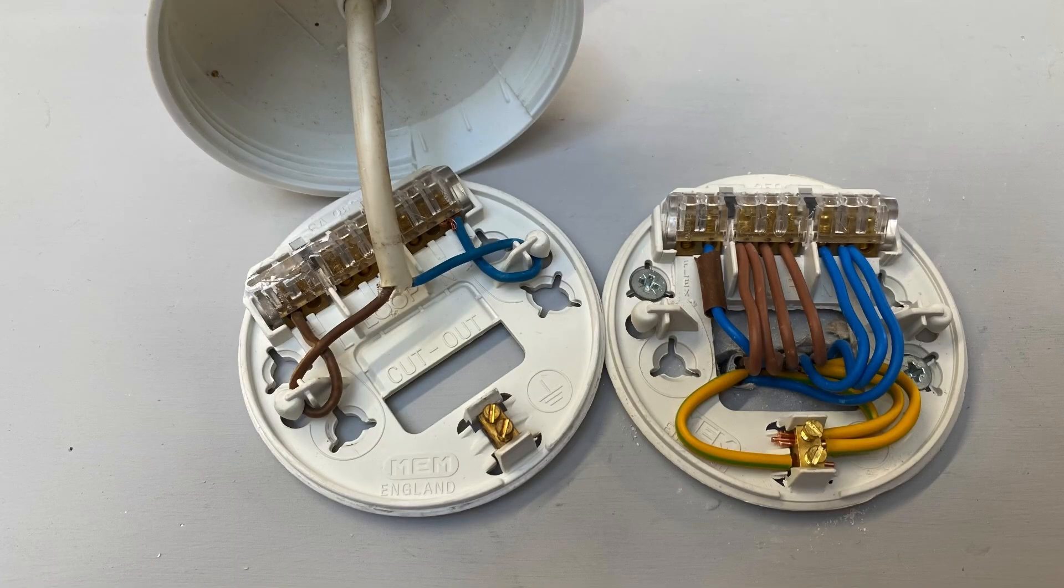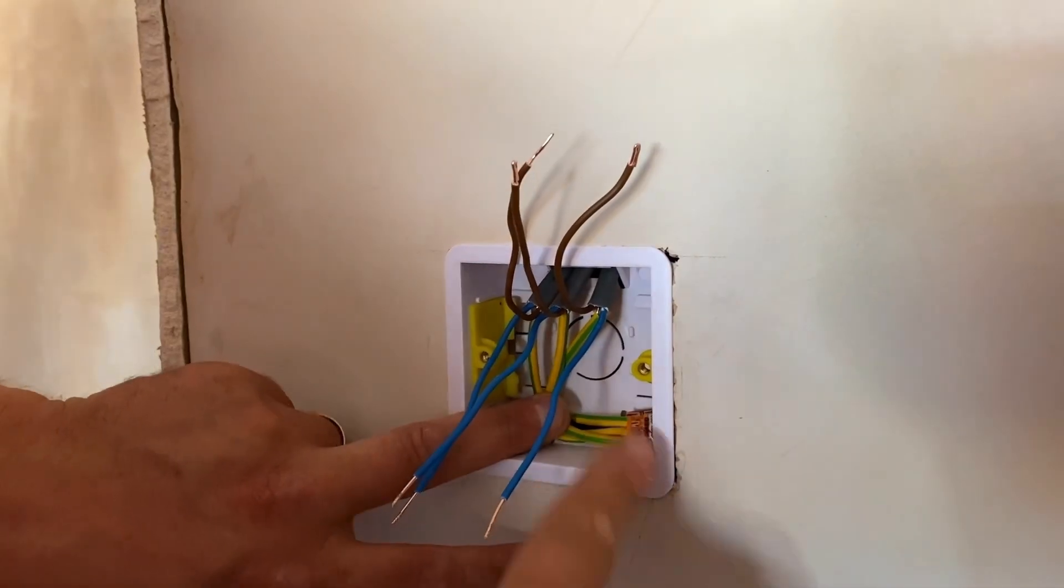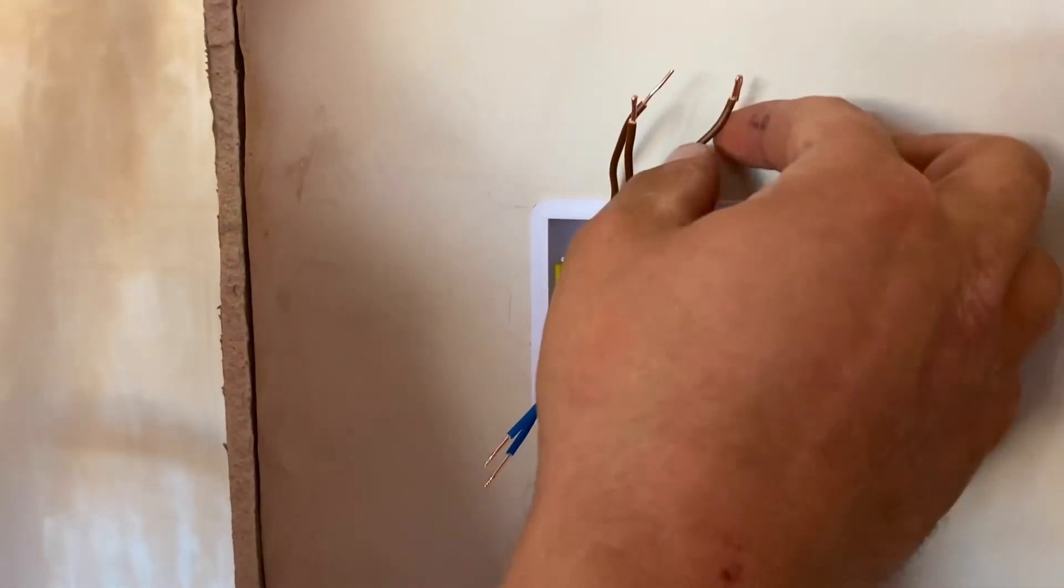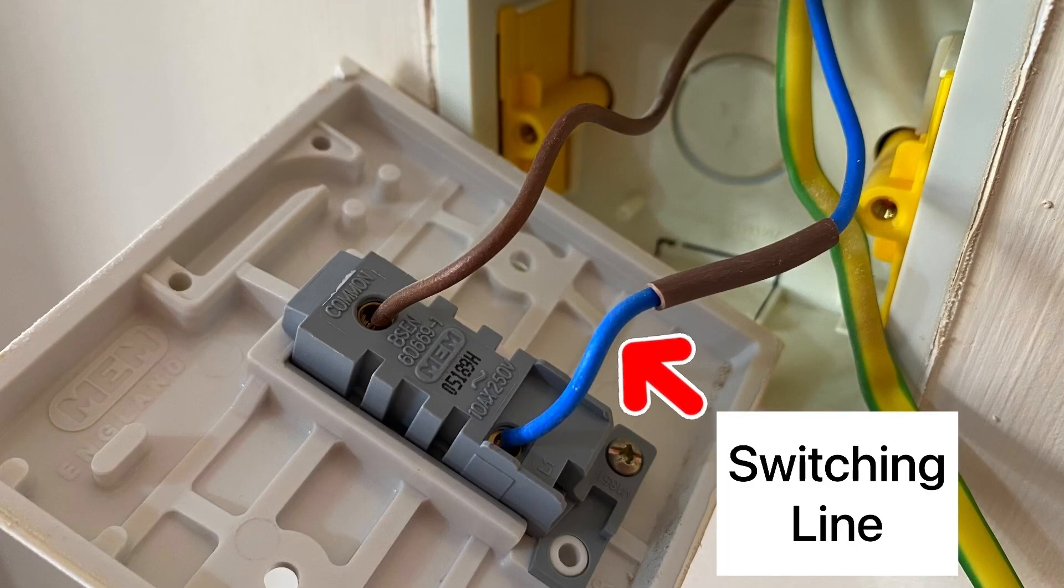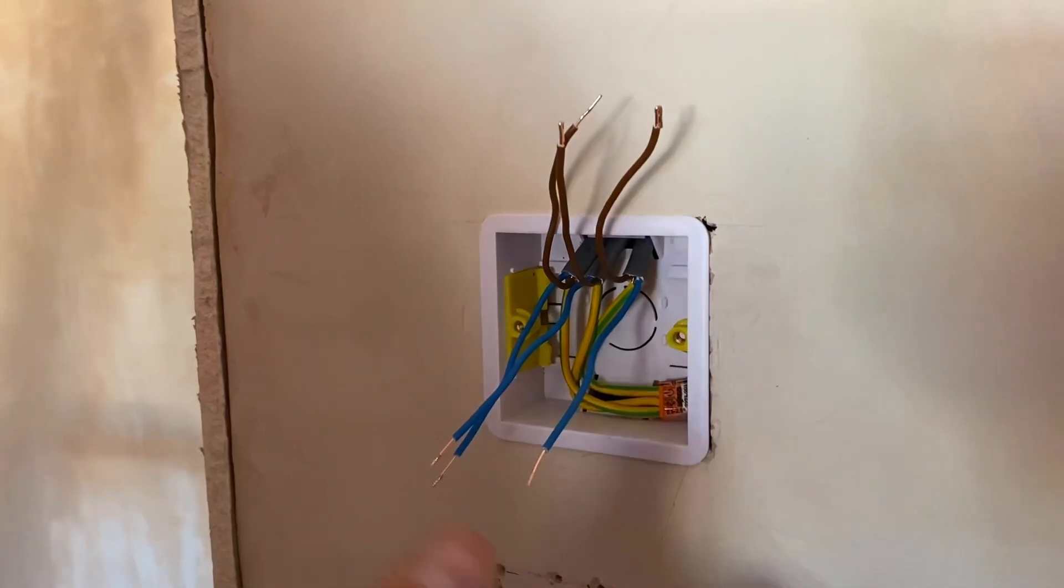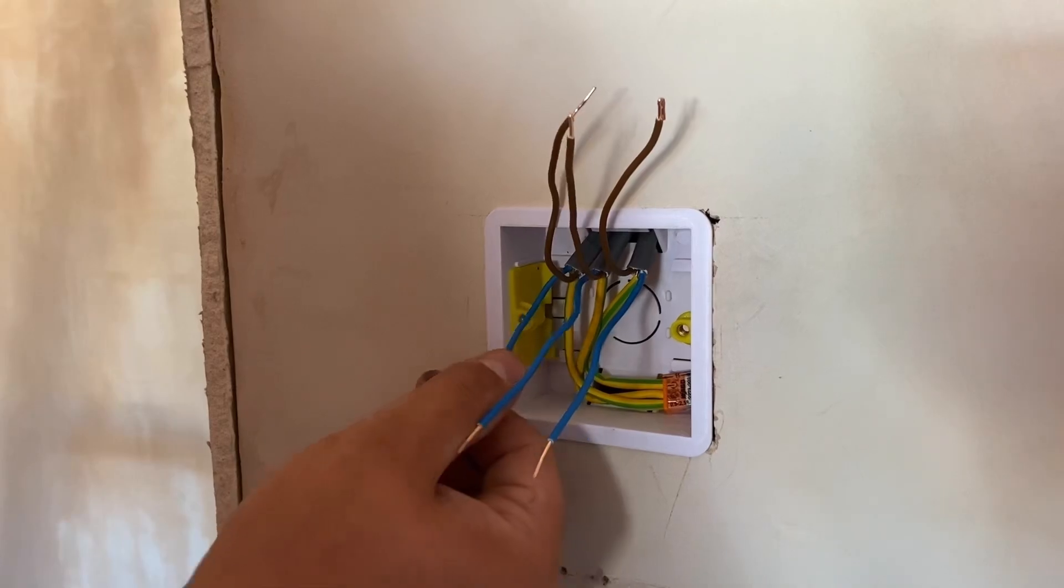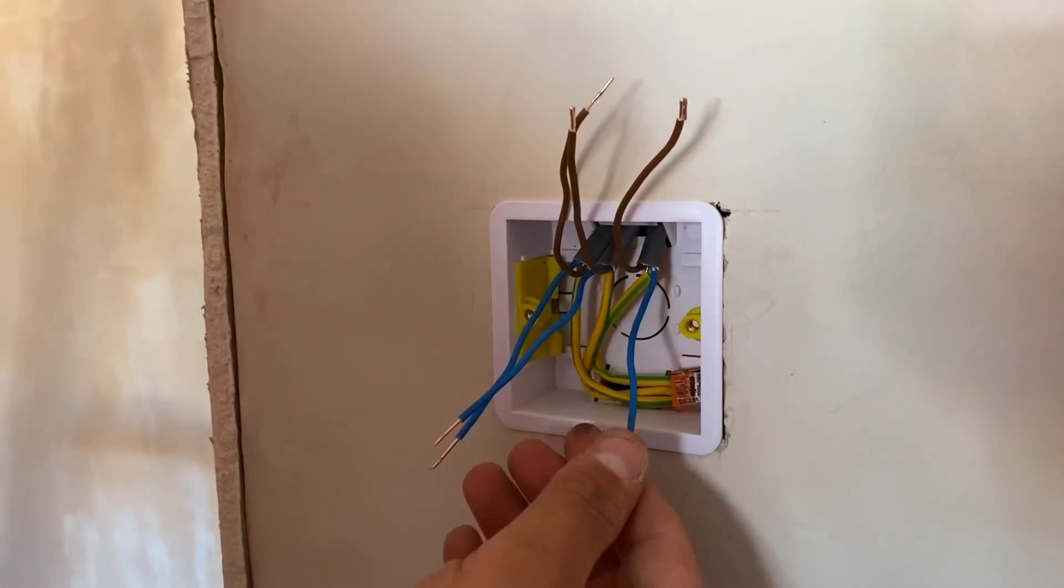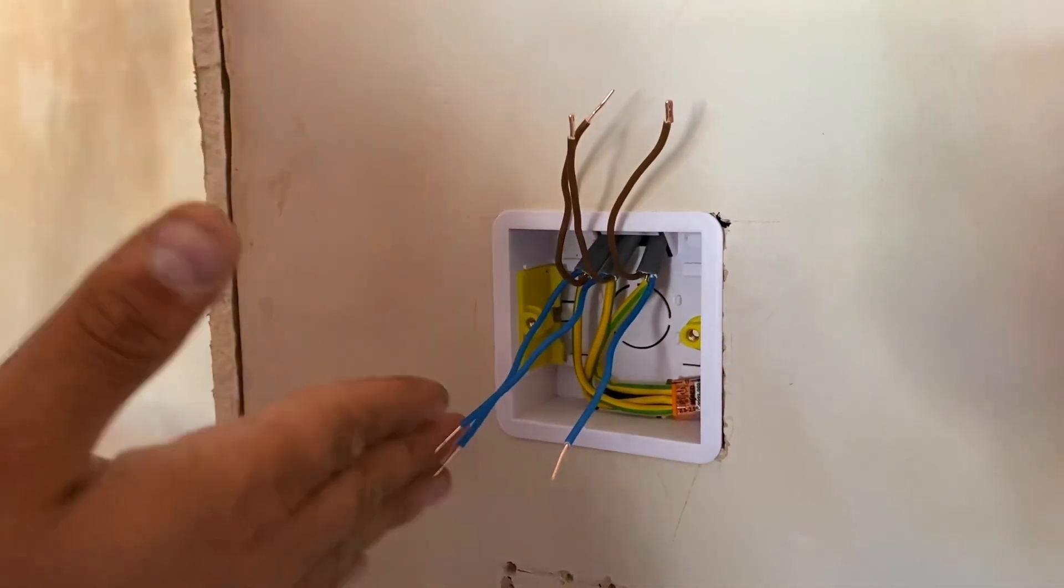As you can see here, usually we used to maybe be seeing one brown, one blue conductor, this blue conductor being sleeved as a switching line. But because we've fed the switch now, we actually have three cables in here. Now that could be a feed in and then a feed out, but actually on this one it's not. So we've only got feed in because this is the last point.